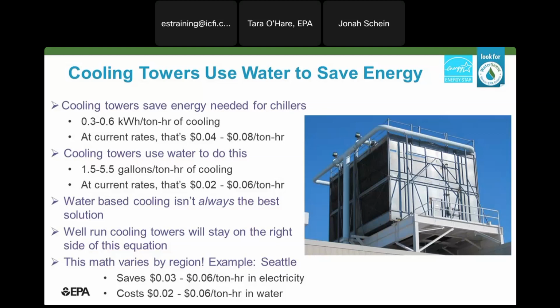The flip side of that is that in order to get that energy and the cost savings associated with it, we are going to use water, and that's going to be somewhere between 1.5 to 5.5 gallons per ton hour of cooling. So every half gallon or half kilowatt hour per ton hour of cooling that we save is going to use somewhere in that range of gallons in consumption, and that at current national rates is about 2 to 6 cents. So you'll notice if your point is to save operating costs with a cooling tower, these numbers overlap. If you have an inefficient cooling tower and you think you're saving money because you're reducing your energy bill, you might not be, because if you're using more water, which is still cheap but not as cheap as it used to be, then you might not be coming out in the black, as they say. So water-based cooling isn't always the best solution.